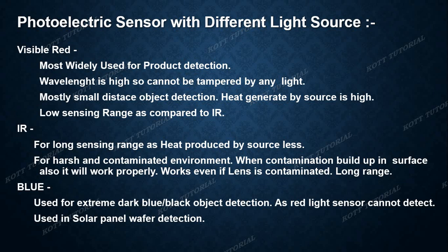So for that application we use the infrared source photoelectric sensor. Now the third type is blue light source. See, the blue light source we use for a perfect black body. If I have to detect any object or a target which absorbs the complete light incident on it, at that time we have to opt for blue light source photoelectric sensor.